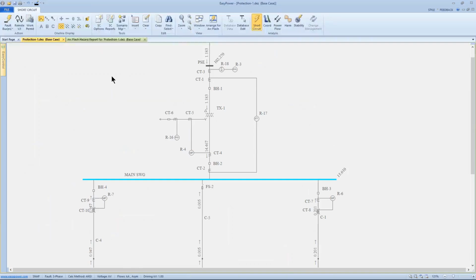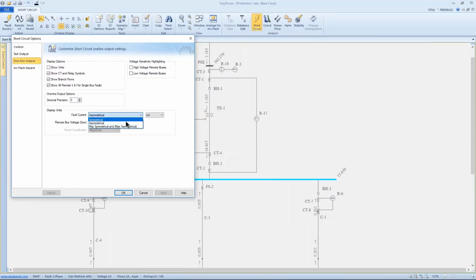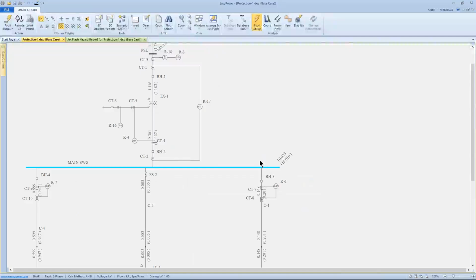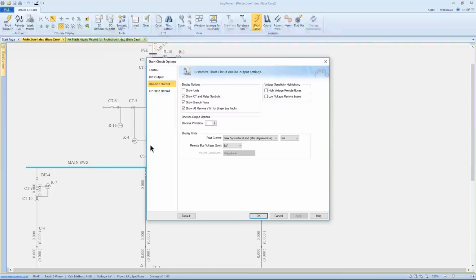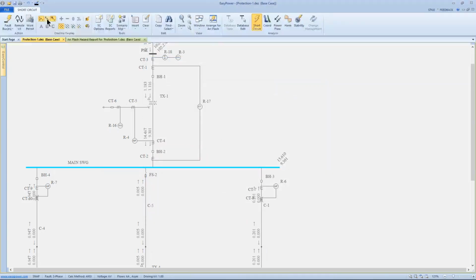All right, so that's asymmetric. Finally, if we want to show the combination of asymmetric and symmetric, or the comparison, we can show max asymmetric and max symmetric. As we do that, we get two values, looking at the half cycle point: symmetric will be 10,000 amps, asymmetric will be 15,000. If we look at 5 cycles into it, we'd expect to see a lower value for the asymmetric current, and then they should be equal at the 30 cycle point, which we in fact do see. We can't show all three of them in the display, but if we come back to short circuit current and show just asymmetric, we can see that decline over time.